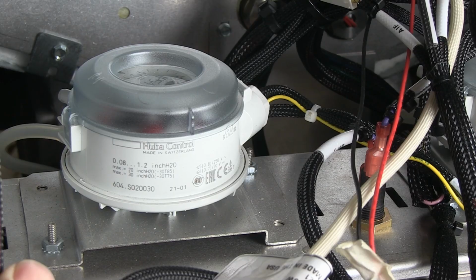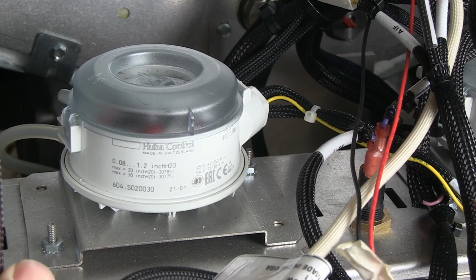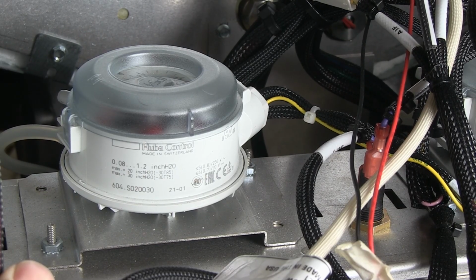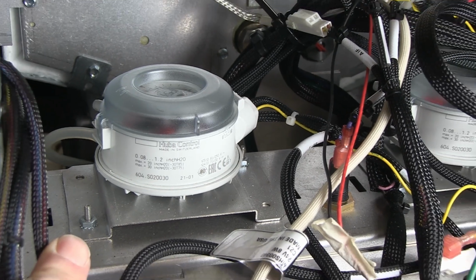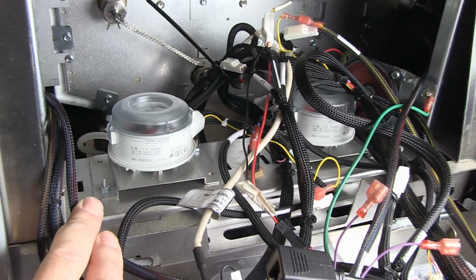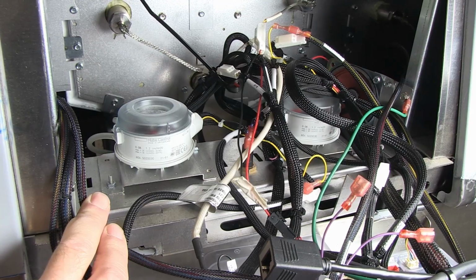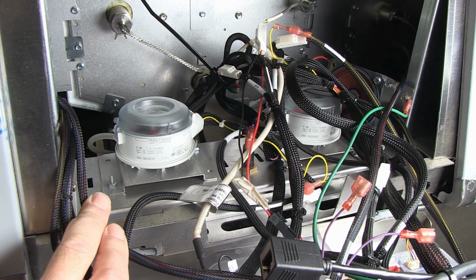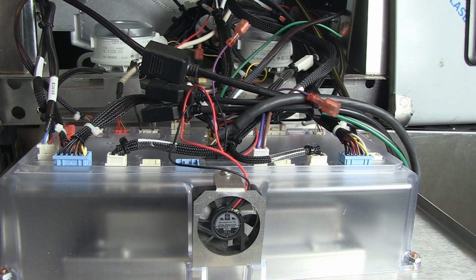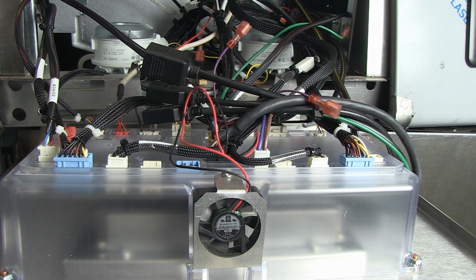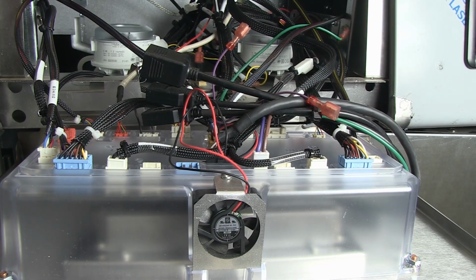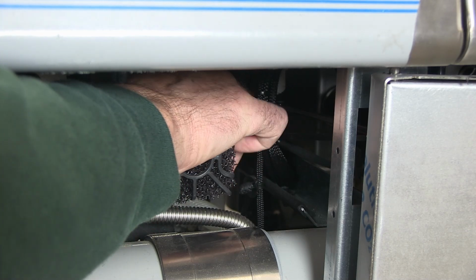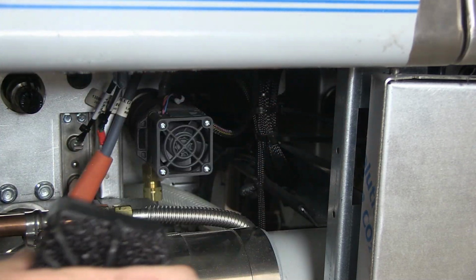Also in the control box are pressure switches. They are key to the operation of the fryer. They monitor the output of the blowers that feed air into the burners. As the blowers' filters grow dirty, the pressure the blowers generate diminishes. The HCB, which is monitoring the burners via the air pressure, increases the RPM of the blowers. When the fan efficiency falters, the controller calls for the filters to be cleaned.